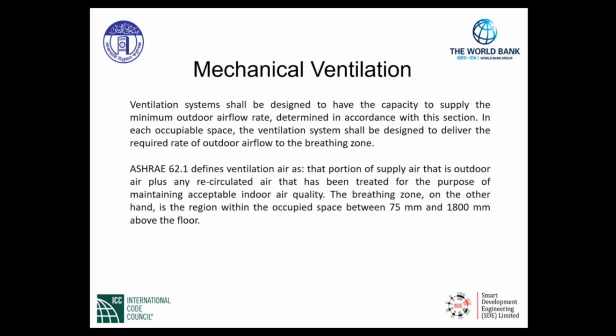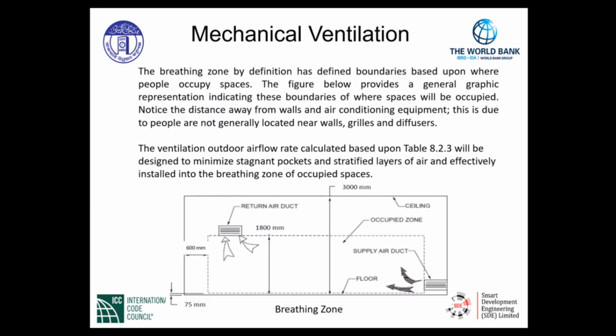The breathing zone, on the other hand, is the region within the occupied space between 75 millimeters and 1800 millimeters above the floor. The breathing zone, by definition, has specific defined boundaries based upon where people occupy spaces. As seen in the figure below, a general graphic representation indicates these boundaries. Notice the distance away from walls and air conditioning equipment. This is because people are not generally located near walls, grills, and diffusers.